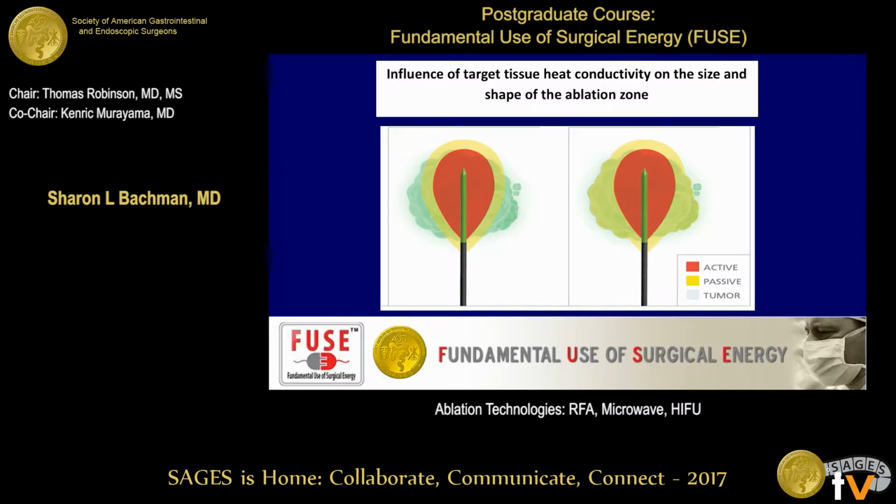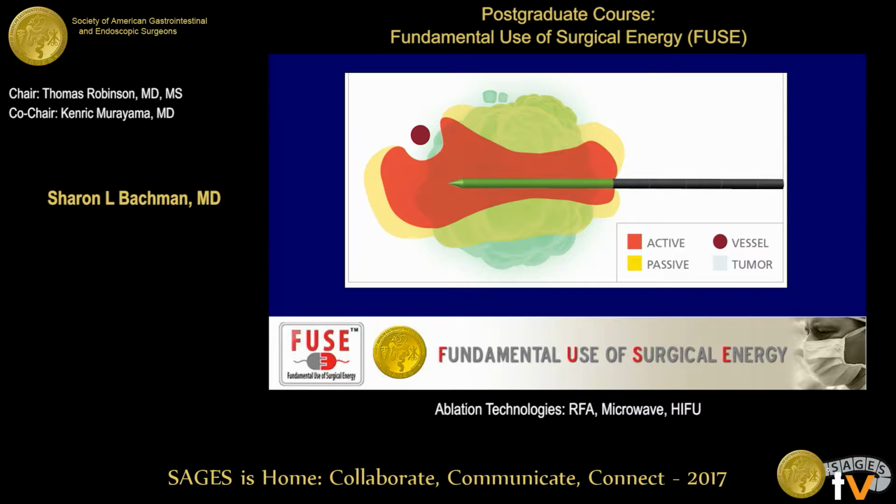So there's a physical constraint to the area that you get your effect. And as you can see in these pictures, the tip of your device and the tissue are both going to lead to how the tissue is affected. And so you really have to pay attention to where your lesion is and what kind of tissue it's in as how you select the appropriate device. And we'll talk about this in a minute, but nearby structures can also affect your field as well.